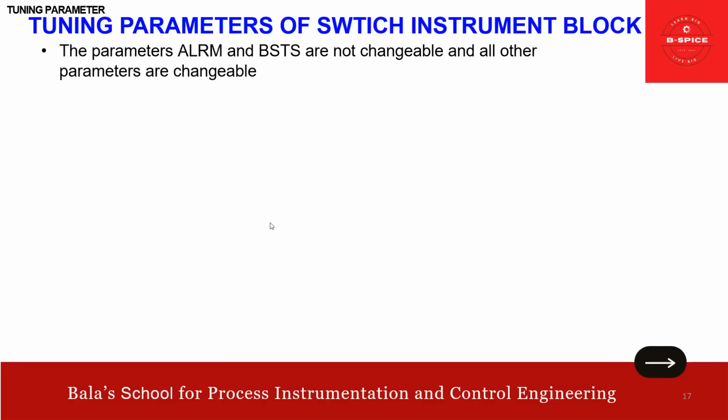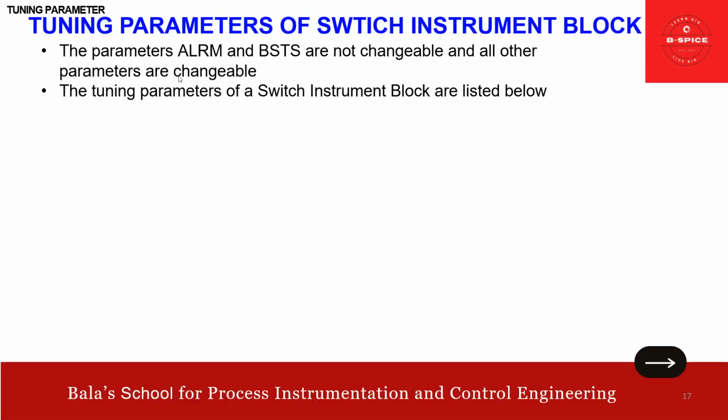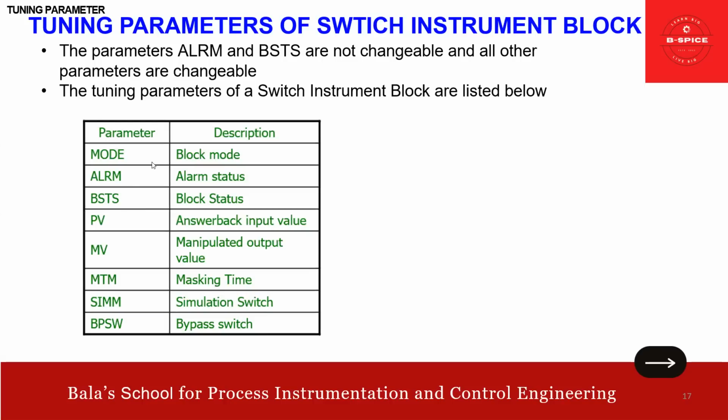Now we'll see the parameters. Basically the parameters alarm and BSTS are not changeable, and all other parameters are changeable. You can see here, mode can be changed, alarm status cannot be changed, BSTS cannot be changed. PV can, PV answer back input value, MV manipulated value, masking time, simulation, bypass, all these can be changed.